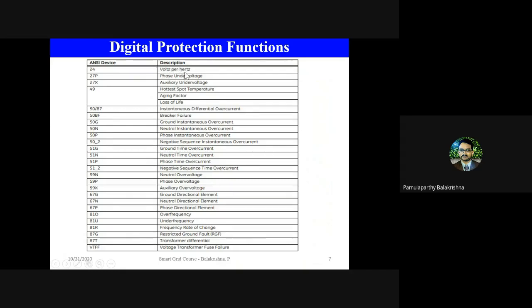Okay, so these volts and frequency signals in a normal relay, meaning without 61850, the data can be written in any format by the operator. He can write any name for voltage or any name for frequency. It is not a standardized name. Whereas in a 61850 enabled protection device, the names that are used for voltage and frequency will by default be as per the standardized names given in 61850. And for all the protection functions, there is a corresponding logical node which defines the standardized names of the signals that are required and the control that is required for each of these protection functions. So basically, 61850 standardizes the naming conventions of the signals, measurements, and the control parameters that are required by each of the protection functions. Whereas the ANSI or the IEC standard defines how a protection function should be designed or how it has to be executed in the field.